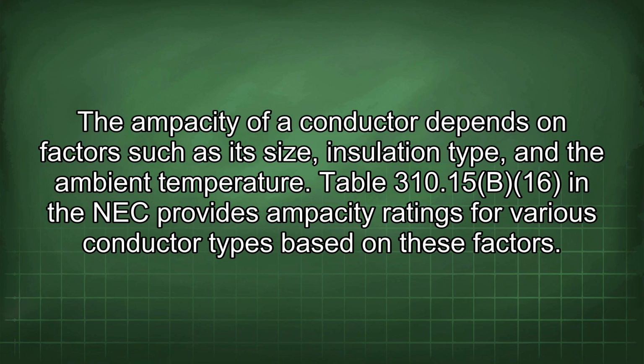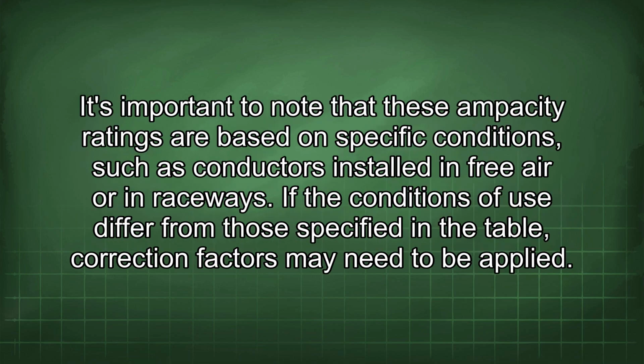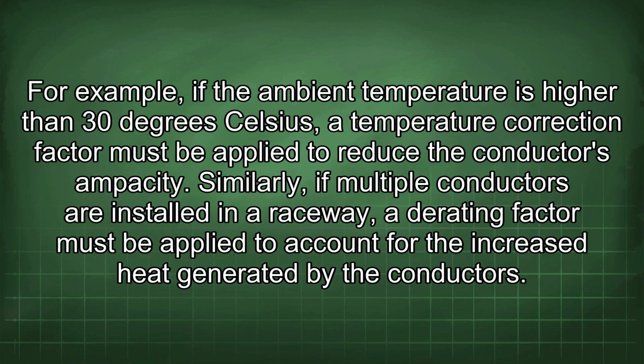Table 310.15(B)(16) in the NEC provides ampacity ratings for various conductor types based on these factors. It's important to note that these ampacity ratings are based on specific conditions, such as conductors installed in free air or in raceways. If the conditions of use differ from those specified in the table, correction factors may need to be applied. For example, if the ambient temperature is higher than 30 degrees Celsius, a temperature correction factor must be applied to reduce the conductor's ampacity. Similarly, if multiple conductors are installed in a raceway, a derating factor must be applied to account for the increased heat generated by the conductors.